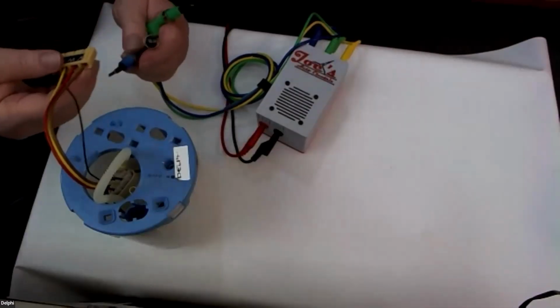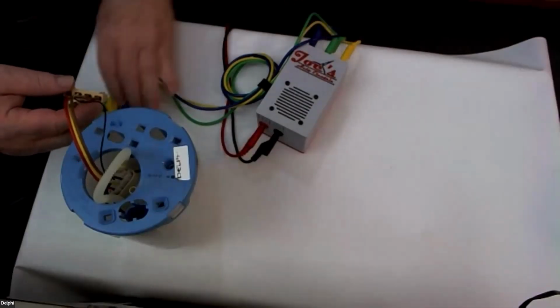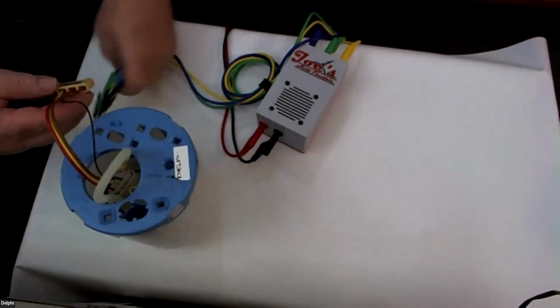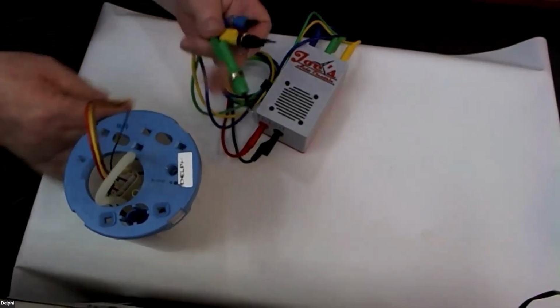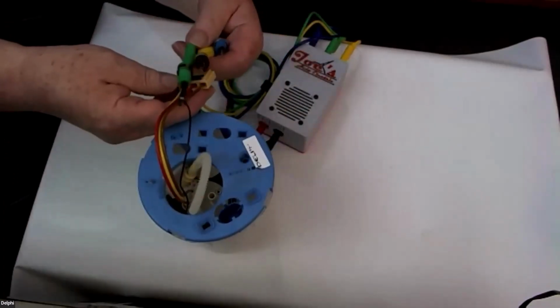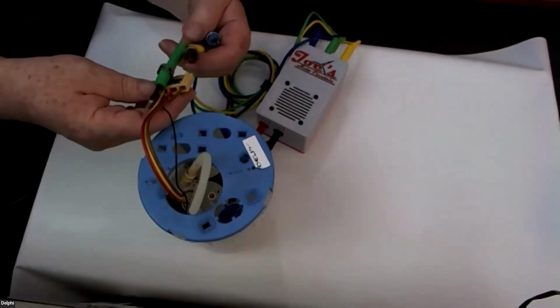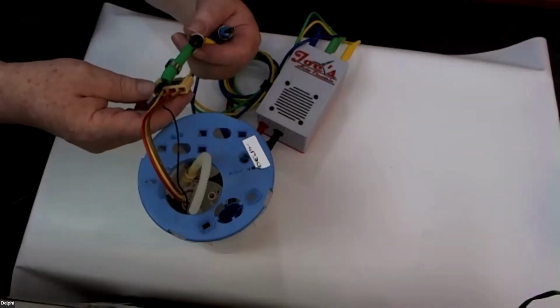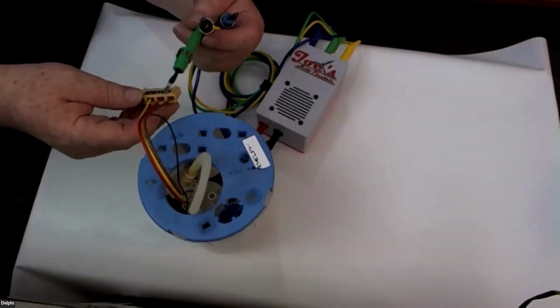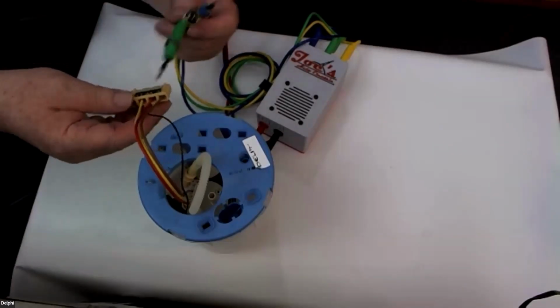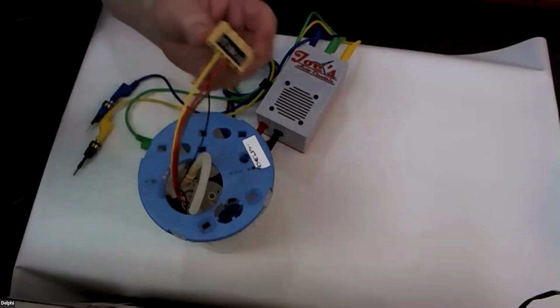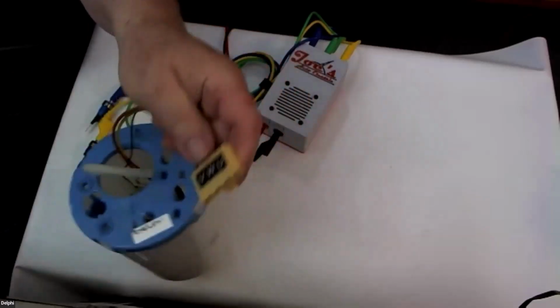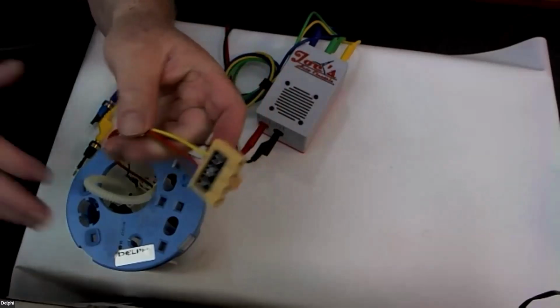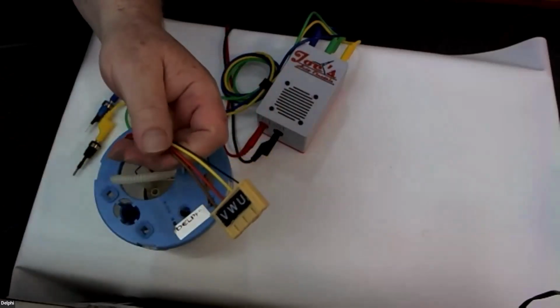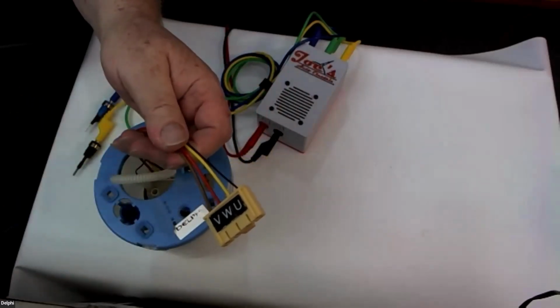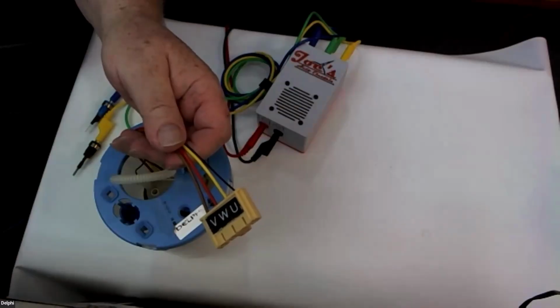I want a good connection, and I also want to make sure these are color coded. Now, the colors obviously don't match here—I don't have a green and a blue wire, I've got yellow, red, and brown. But I did keep the markings, whether it's 1, 2, and 3 like Chevy uses in their service manuals, or at Toyota—very good—they use U, V, and W, which is traditional labeling for any three-phase motor.